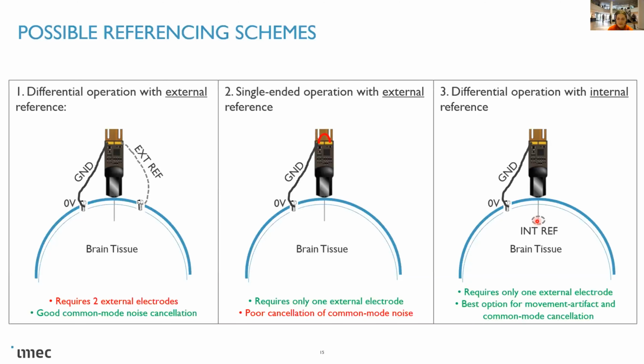Maybe something I didn't mention regarding the internal reference electrode, and that will happen also with the averaging, is that you may cancel common LFP signal depending on how much of an average you do. That happens also with the internal reference electrode: you will cancel out LFP signals that are closer to the internal electrode. So if your application is LFP, grounding can have other difficulties, and only having an external reference electrode is the best option. But averaging and using an internal electrode should be pretty similar for the rest. Okay, thank you very much.